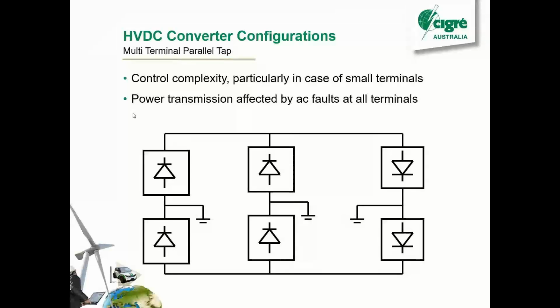Multi-terminal. So yeah, as I said before, it'd be probably less than 1% of LCC schemes that use multi-terminals, because it's quite problematic. A lot of the controls become really complex, even with only 3 terminals. And if you have AC faults, that's going to impact your power transmission at all of your terminals, which isn't ideal.